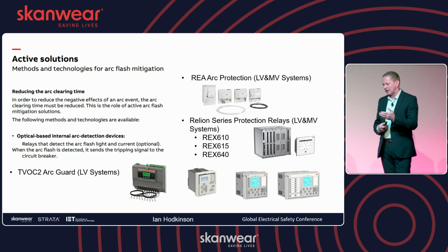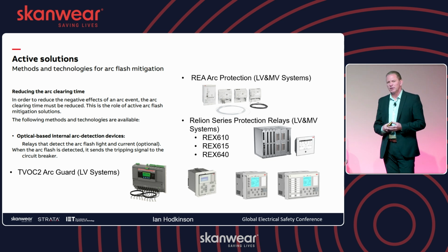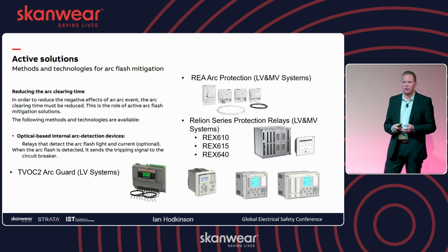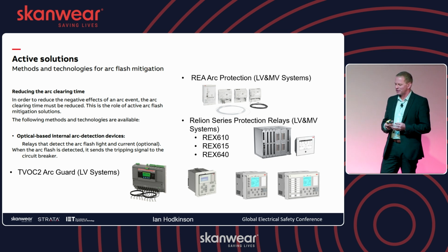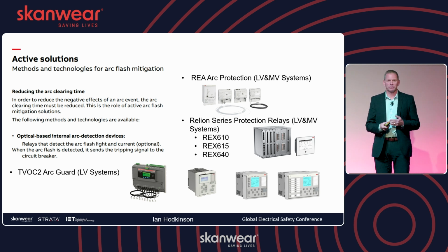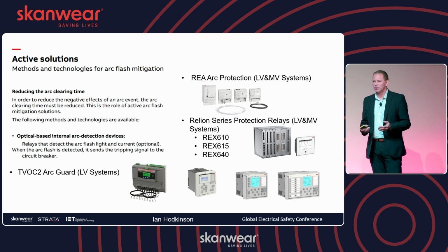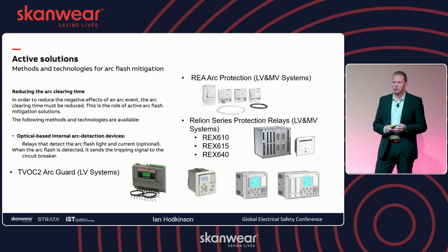We also have a standalone system, which is the REA. This is a combination of centralized units and extension units, so you can have full coverage. This is perhaps what we'd say is good for a new board, but also good to retrofit because you can add it on top of your existing protection, especially if you're worried about your outages being too long without having to fully replace everything. You can just add it on top of your existing protection. Don't touch the grading, don't touch the relays, your scheme when you're wiring. It's just an addition for doing arc protection only.